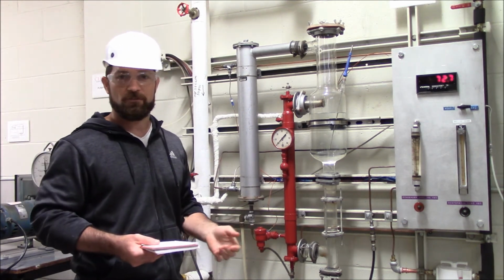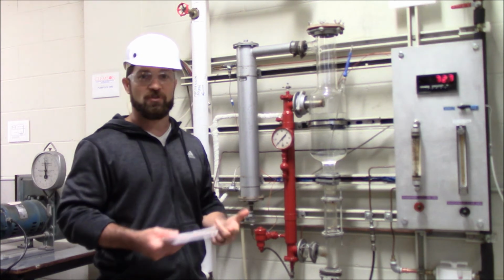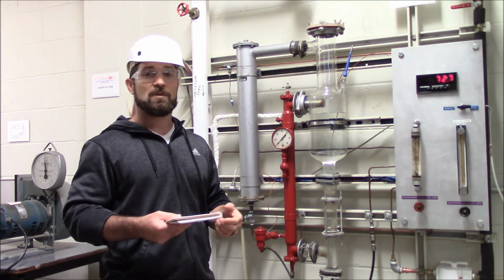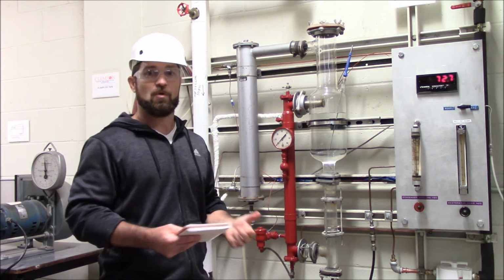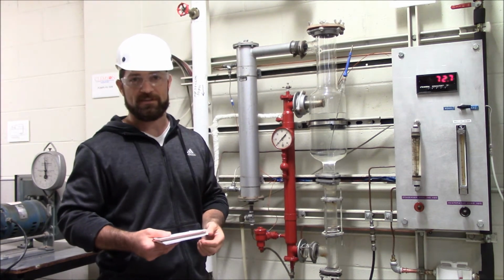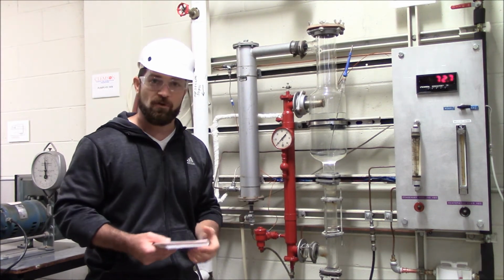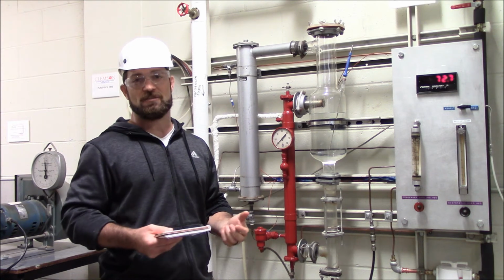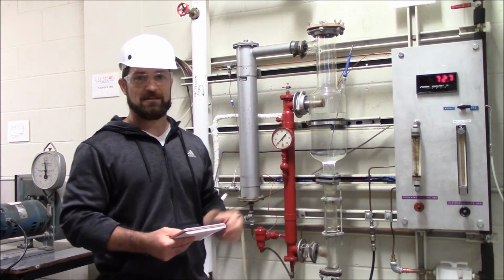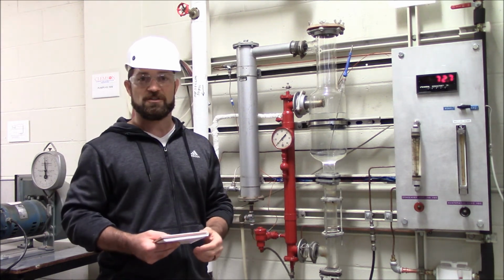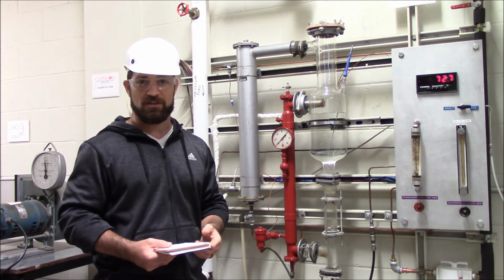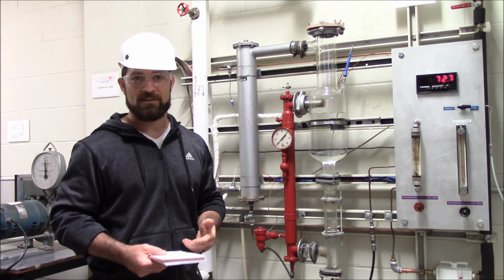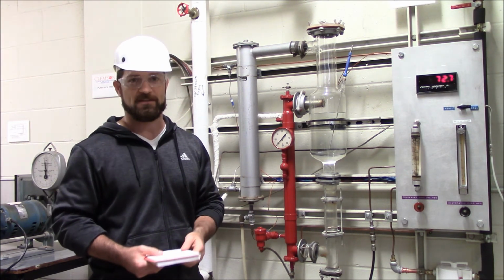Now, using these different flow rates and the temperatures, you can use your energy balances to determine the amount of heat added to or removed from the various components of the system, and then combined with your overall energy balance, you can determine the heat transfer coefficient for the system. Using the heat transfer coefficient, you can do your design scenario calculations and determine the right evaporator that's necessary to do the job that's requested.